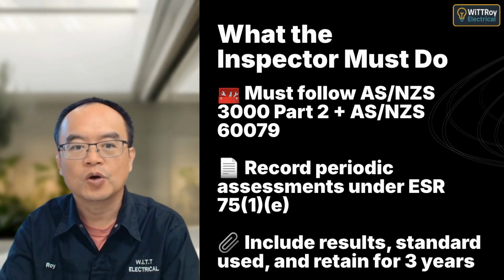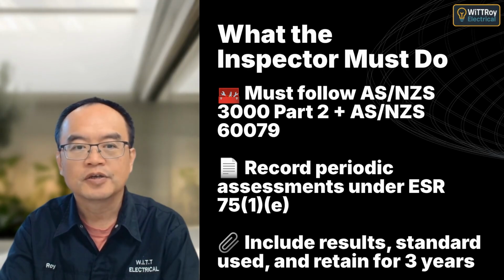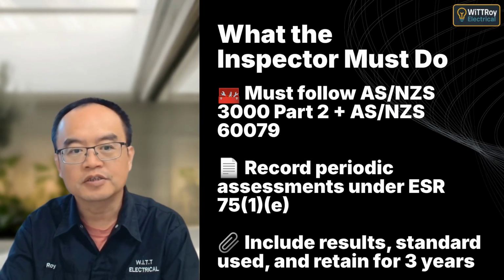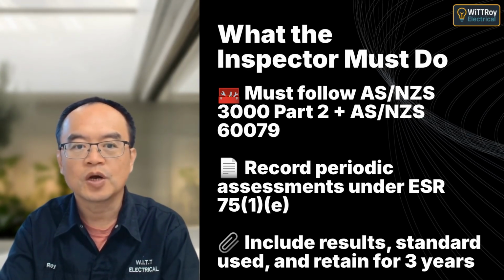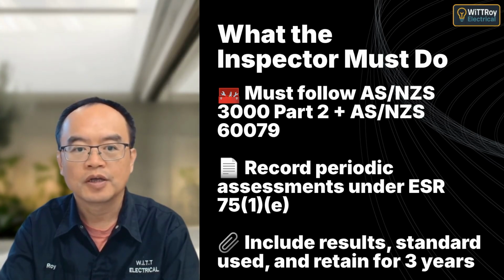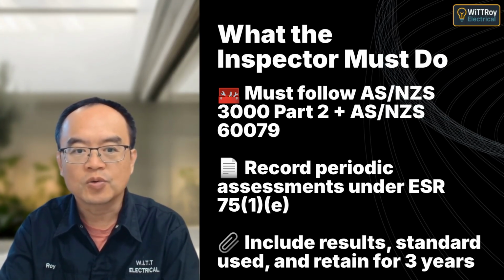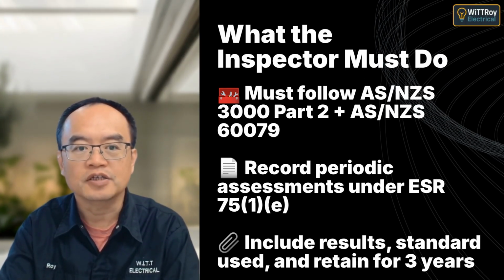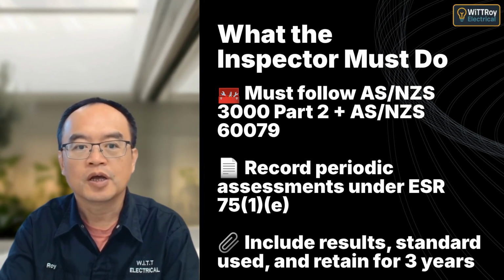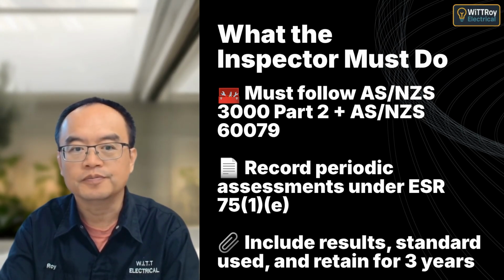When inspecting or maintaining installations in hazardous areas, you must follow the relevant standards and create a record of assessment as required under ESR 75(1)(e). This includes stating which standard was followed and, under ESR 75(4), keeping a copy for at least 3 years, or sending it to WorkSafe.